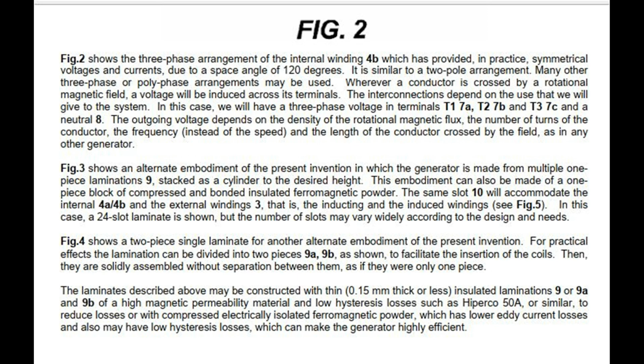In this case, we will have a three-phase voltage in terminals T1 7a, T2 7b and T3 7c and a neutral 8. The outgoing voltage depends on the density of the rotational magnetic flux, the number of turns of the conductor, the frequency, instead of the speed, and the length of the conductor crossed by the field, as in any other generator.